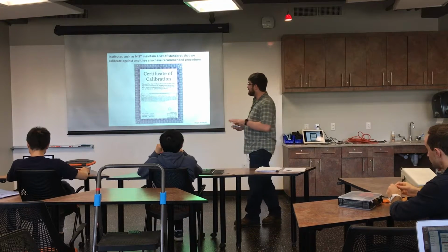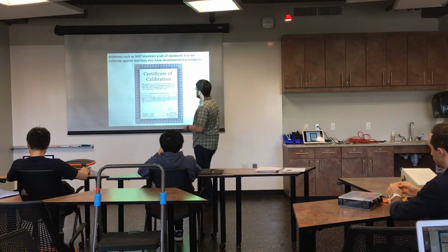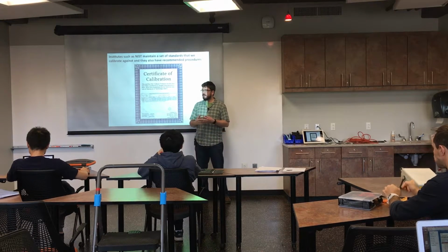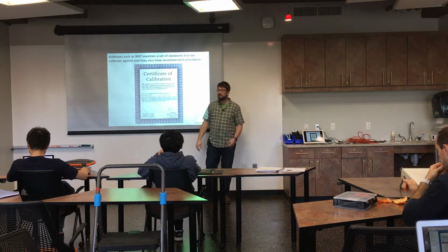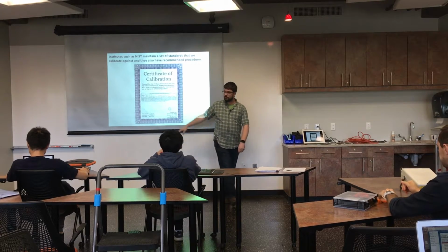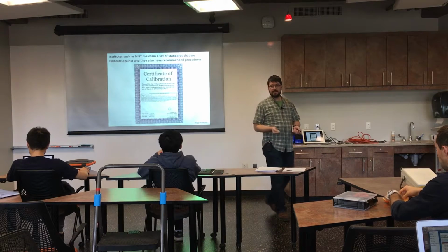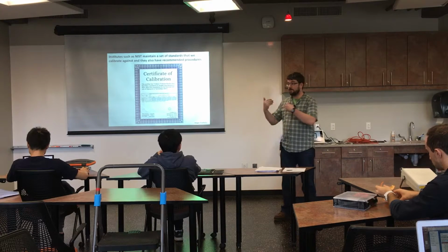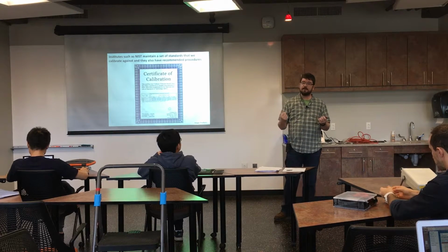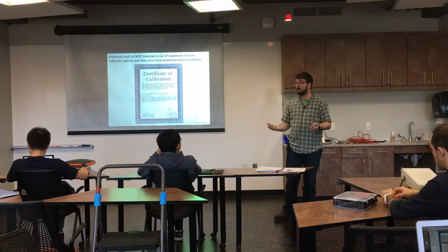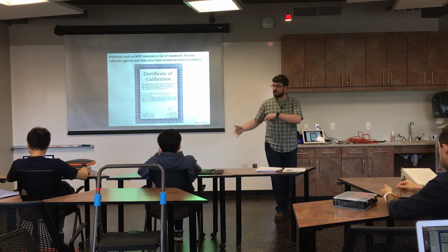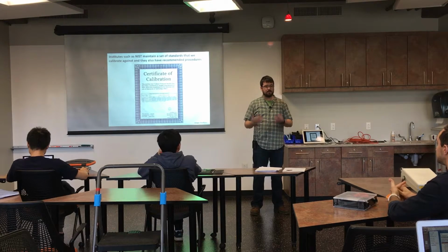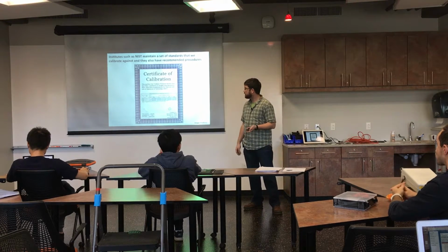But really, if you need an absolute calibration, you need to be able to trace it back to the National Institute of Standards and Technology, which is NIST. And when you get something that is certified by them or certified to be in compliance with their standards, it comes with a nice little certificate like this, and you want to hold on to that because you're using this as a transfer standard. Meaning we don't have in the laboratory the standard meter, or the standard kilogram. There's only one, right? But we have a transfer standard that's been calibrated against that, and we can use it as truth in the laboratory. So we're using it to transfer the information from that standard to our instruments.